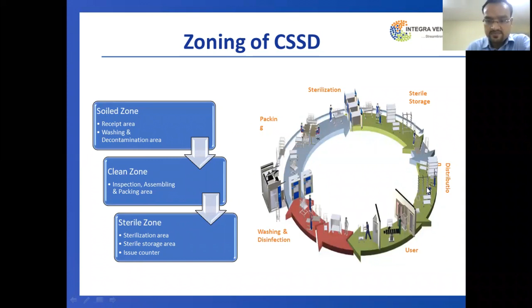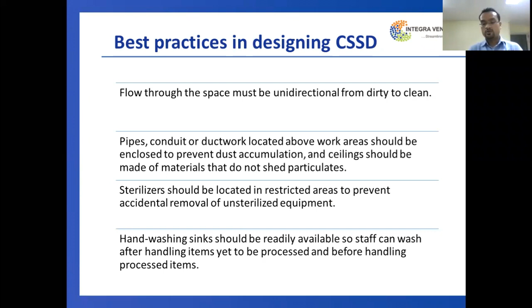If you look at the basic design of a CSSD, the flow through the space must be unidirectional, from dirty to clean. Pipes, conduit, or ductwork located at work areas should be enclosed, sealed, and concealed to prevent dust accumulation. Ceilings should be made of materials that do not shed particulates. Sterilizers should be located in restricted areas to prevent accidental removal of unsterilized equipment, which would lead to improper sterilization of the instruments. Hand washing sinks should be readily available so staff can wash after handling items to be processed and before handling processed items. So adequate hand washing facilities need to be there.